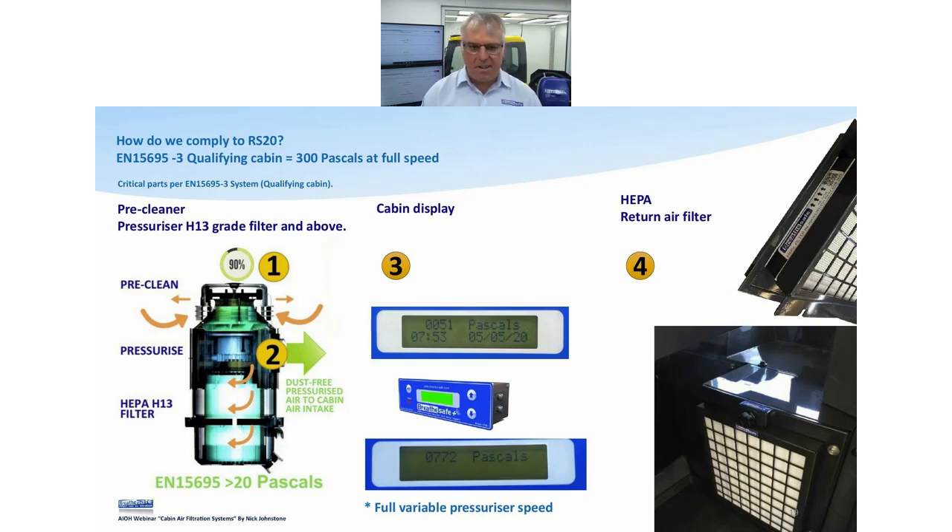The only way to know the system is working is with some sort of cabin pressure monitor. The pressures we're talking about are so low — in Pascals — you can't detect them by feel. Ideally your pressurizer should have some sort of pre-cleaning arrangement — centrifugal, topspin, Donaldson cyclone, or similar pre-cleaners — to take out the big stuff and hopefully the majority of inhalable particles. Then you'll have your blower assembly, then your HEPA H13 — or ideally H14, which is what we've moved to — and then the cabin pressure display.